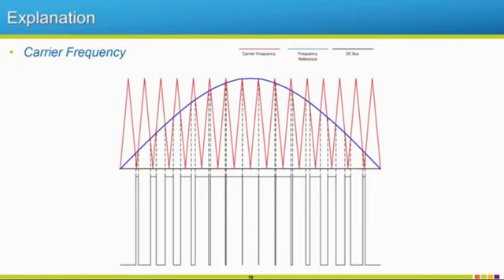I've got a question here. What causes noises in the motor line changing gears? So what causes noises in the motors, carrier frequency. You're going to notice if you run a motor across the line, it's going to be real quiet and nice. And then whenever you run it with a drive, it could be at low carrier frequencies. It could be a little more noisier. That's just the actual vibrations in the laminations that make up a motor that we talked about before. Remember that stator has those little chunks of iron broken up in between there and that's those laminations actually kind of vibrating and making that noise. Now, as you increase your carrier frequency, you're going to notice that that noise kind of goes away. Well, it's just because it goes to a higher frequency that you can't hear or that I can't hear anymore anyways. So that was a good question. So there's carrier frequency.